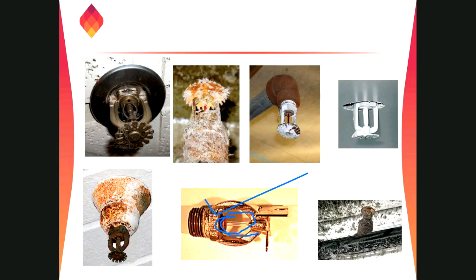Normally, the concept of breaking this bulb is that there is a liquid inside. If that liquid gets heated, it will expand so much that it will break the glass. Now, if there is no fluid, it might break, but at a higher temperature. By the time, the fire will have destroyed the complete building. So no use working for that one. Okay, but how can the fluid be emptied from the bulb?